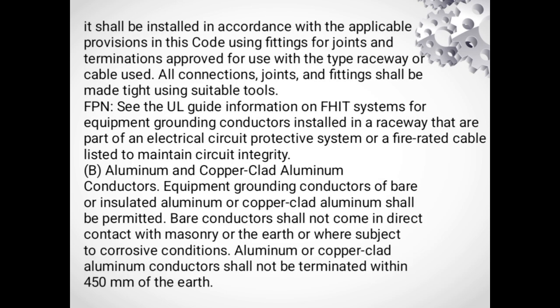It shall be installed in accordance with the applicable provisions in this code, using fittings for joints and terminations approved for use with the type of raceway or cable used. All connection joints and fittings shall be made tight using suitable tools. FPN: See the UL guide information on FHIT systems for equipment grounding conductors installed in a raceway that are part of an electrical circuit protective system or a fire-rated cable listed to maintain circuit integrity. B. Aluminum and copper-clad aluminum conductors. Equipment grounding conductors of bare or insulated aluminum or copper-clad aluminum shall be permitted.